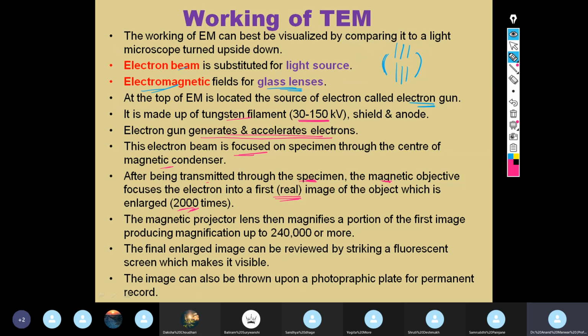If you are using a proper condenser in a light microscope and an oil immersion objective, then you are supposed to get higher magnification of the primary image. Similar is the case here. If the potential of the electron beam generated is higher, or, the other way to say it, if the wavelength is low and the beam is formed, because formation of the beam is dependent on two things. First is the vacuum in the cabinet and second is the function of the magnetic field. If the magnetic field is powerful, it will not allow the electrons to move away from their path. So it will target it.